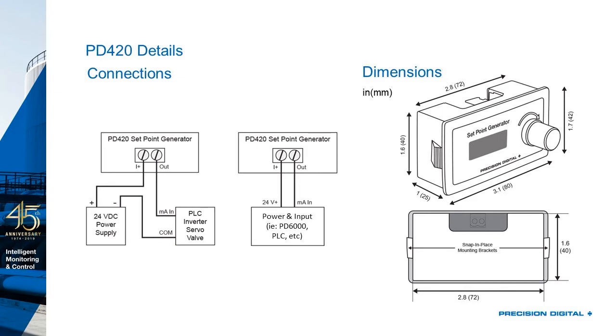Now, if you are using a device that has a power supply already built into it for the 4 to 20 milliamp input, for example, some PLCs will have that. Those of you who have used our ProVu meters know that those all come with a power supply included for the input. Well, then all you need to do is just connect your positive on the 24 volts to your milliamp input. It's 2 wires and you're done.